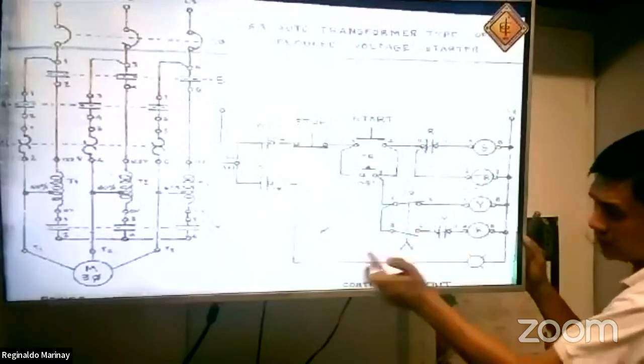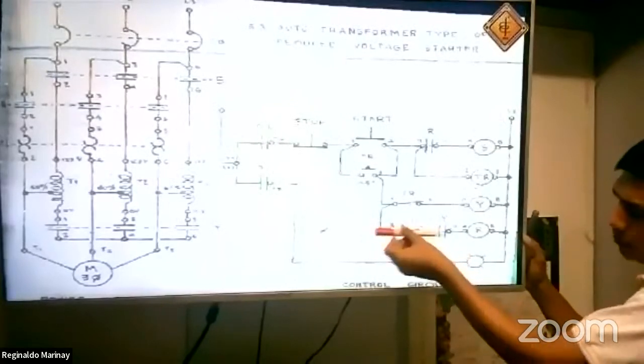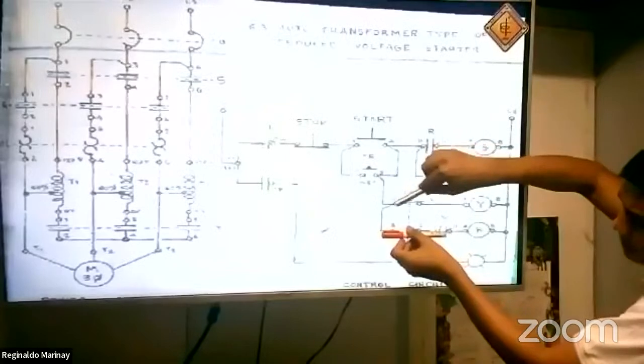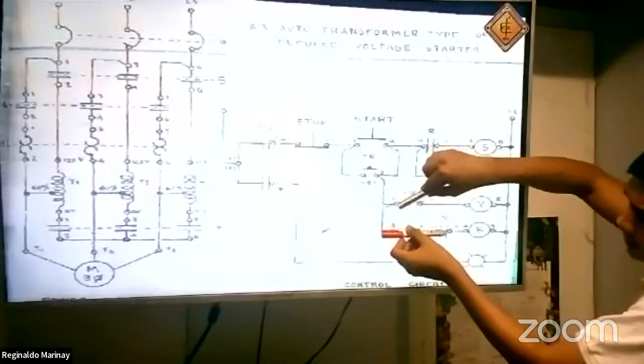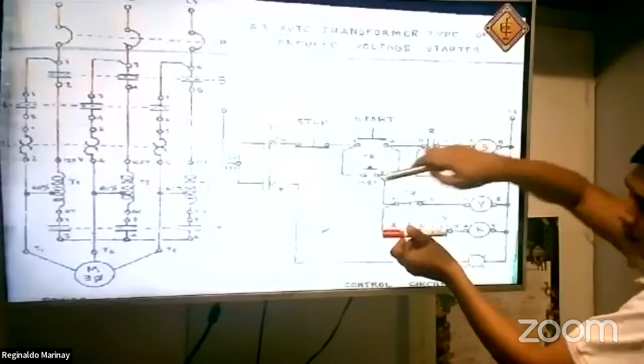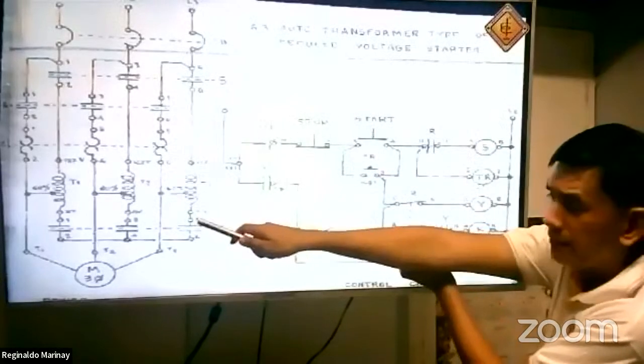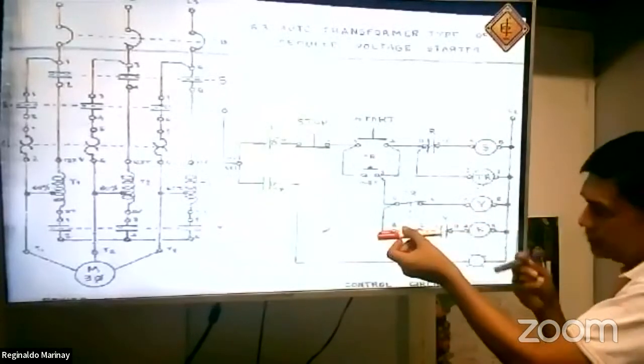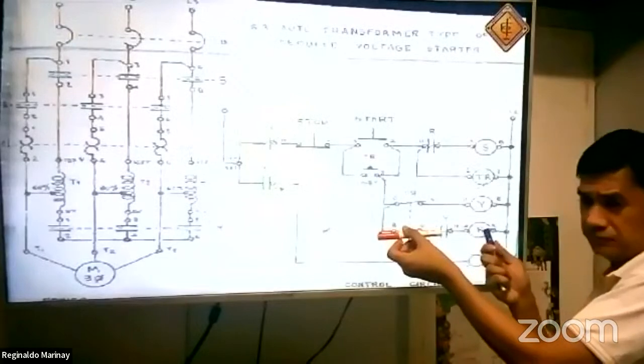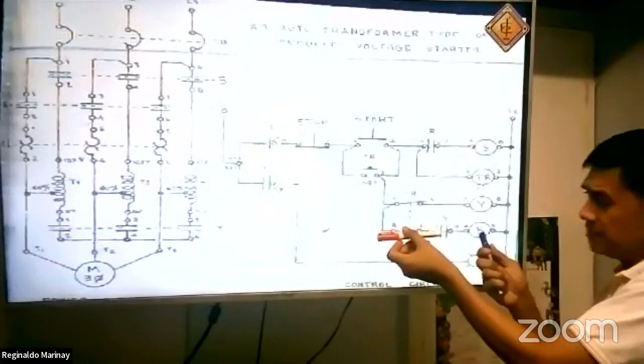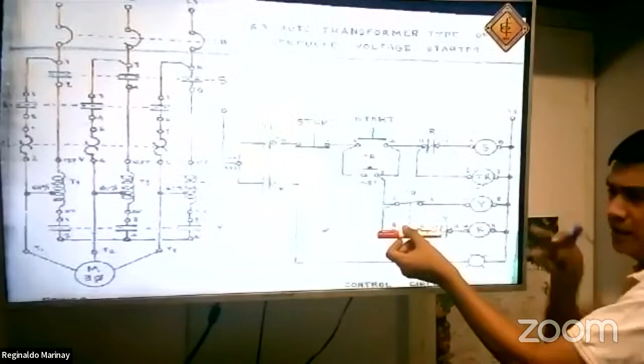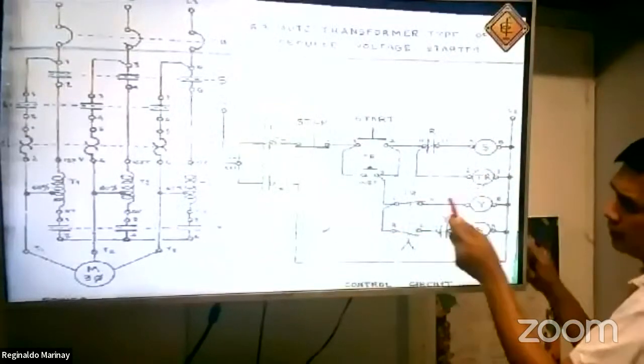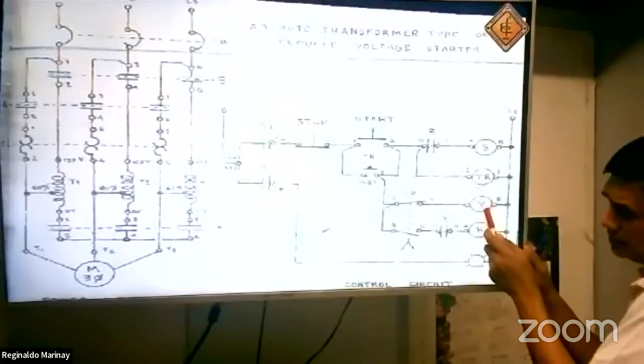You see this open, no? This will become closed. Once this becomes closed, this becomes open. Of course, if this becomes open, this is energized. This Y will become open. The 3Y here, take a look. The R becomes energized. Initially, from 0 to 2.99 seconds, the Y is energized.